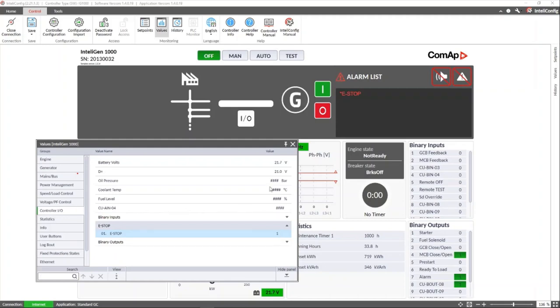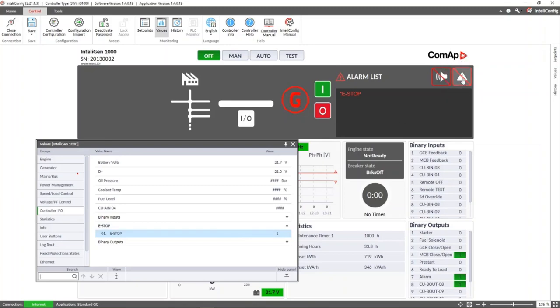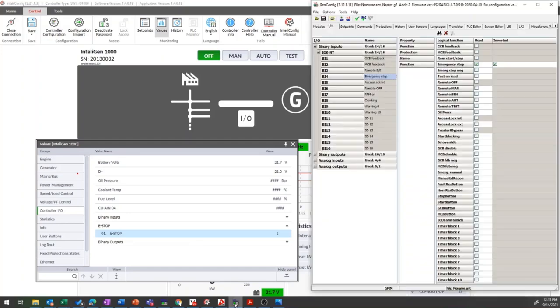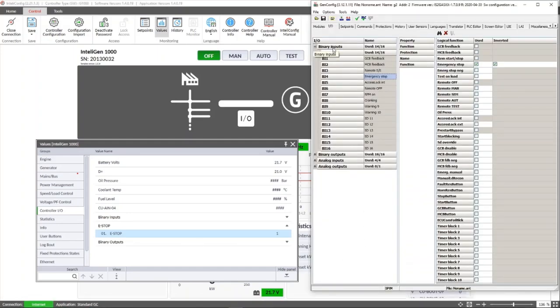We only need to recognize this alarm by pressing the fault reset button so it disappears from the alarm list. In the configuration we don't need to make any adjustments and we simply need to guarantee the connection of the power supply in terminal 4 so the alarm doesn't remain active. And if you want to wire the signal in the traditional way that is done in the InteliGen NT controllers, you only need to configure one of the binary inputs with the emergency stop function.